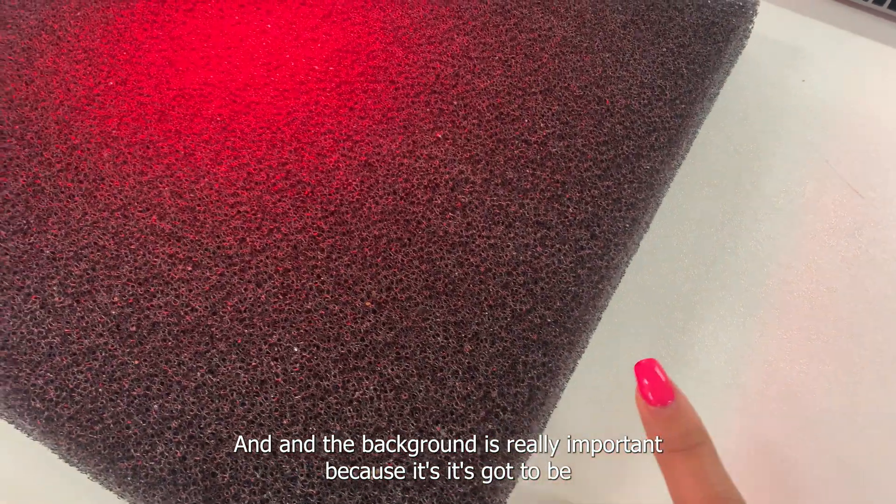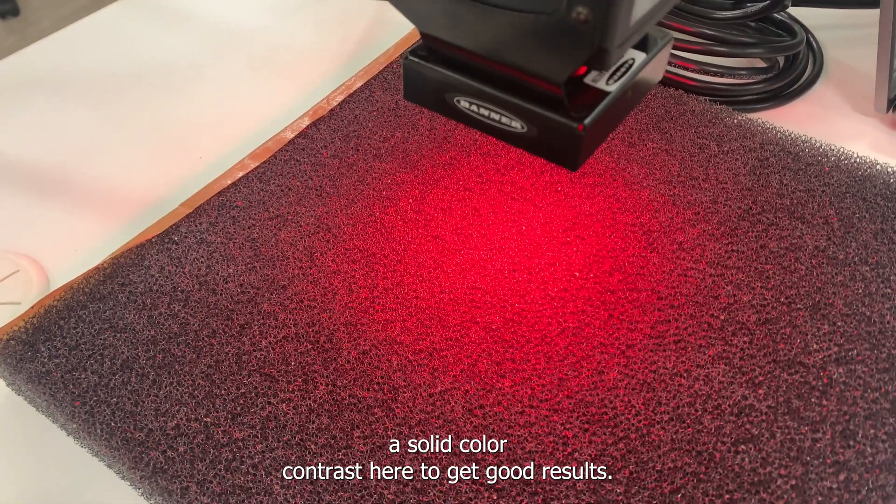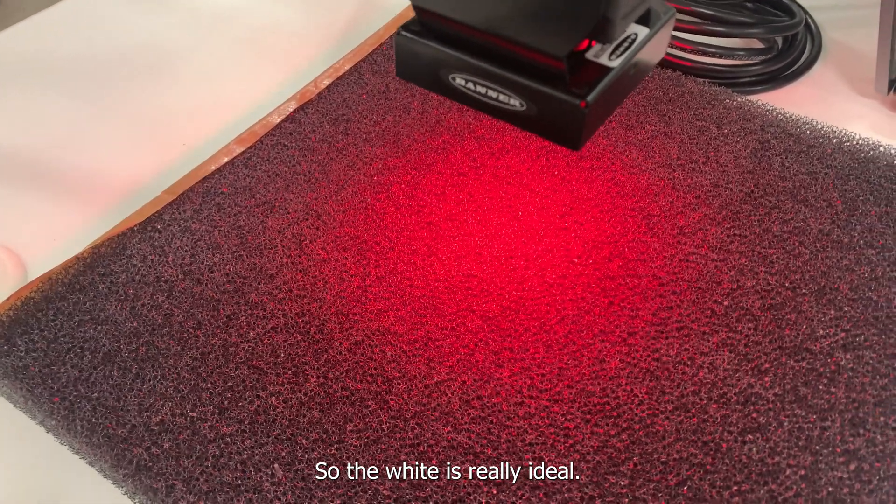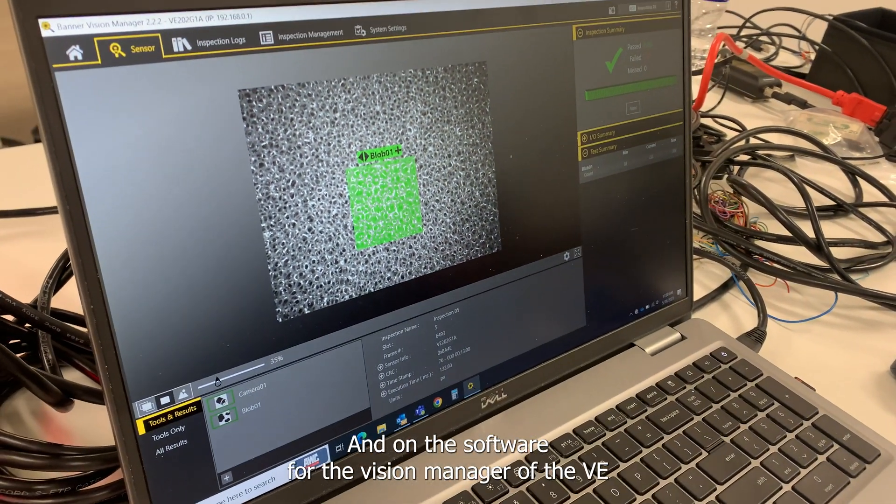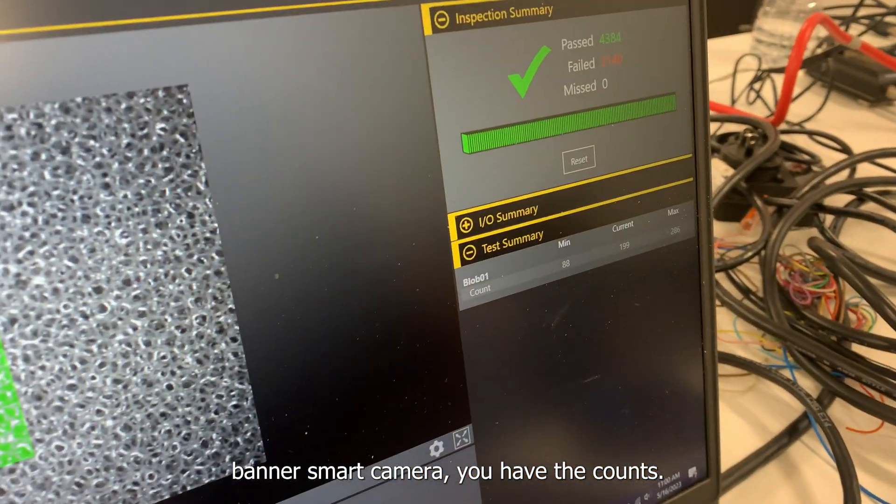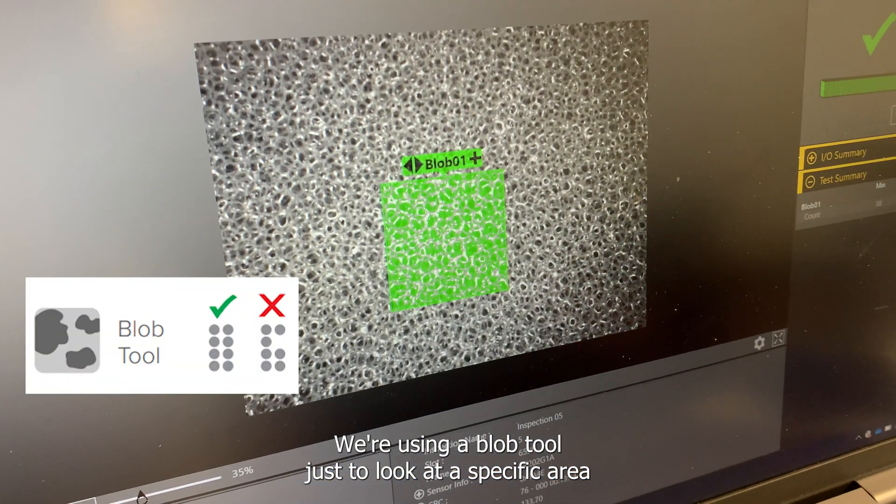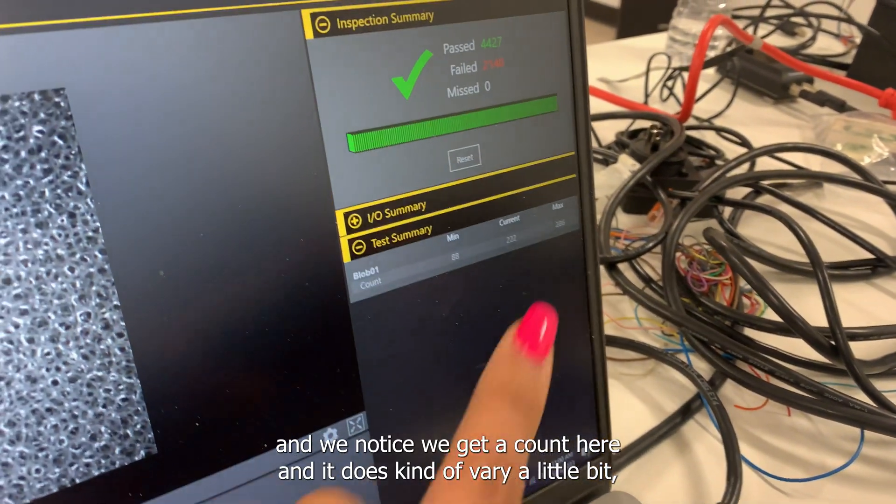On the software for the vision manager of the Banner camera, you have the counts. We're using a blob tool just to look at a specific area and we notice we get a count here. It does kind of vary a little bit, but that can be easily resolved with averaging on the PLC.